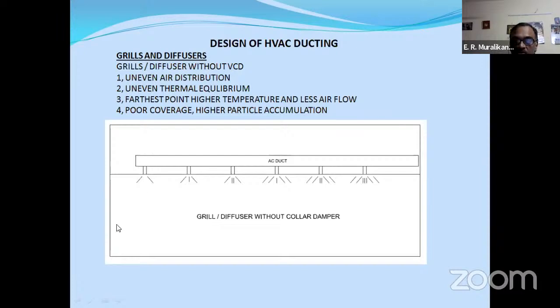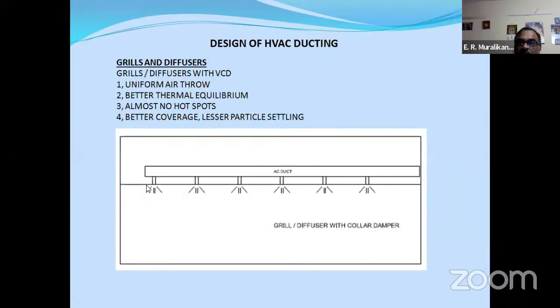So what will happen is this point will be warm and this point will be cold. It will be around a 2.5 degrees centigrade difference roughly in large rooms from this point to this point. So what people will do is put some additional wall mounted fan, ceiling fan or table fan to make themselves comfortable. You are spending some money for the table fan or ceiling fan since you have not put any damper here. It's a recurring cost. Every month you have to pay some money for the EB.